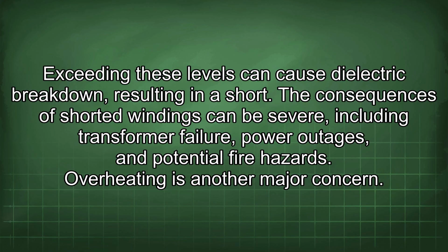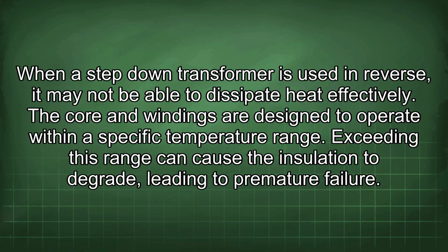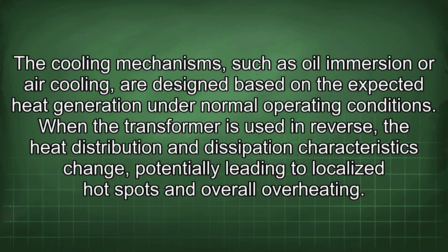Overheating is another major concern. When a step-down transformer is used in reverse, it may not be able to dissipate heat effectively. The core and windings are designed to operate within a specific temperature range. Exceeding this range can cause the insulation to degrade, leading to premature failure. The cooling mechanisms, such as oil immersion or air cooling, are designed based on the expected heat generation under normal operating conditions. When the transformer is used in reverse, the heat distribution and dissipation characteristics change, potentially leading to localized hot spots and overall overheating.